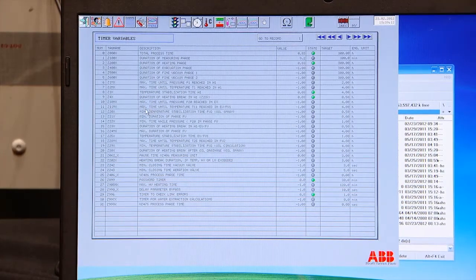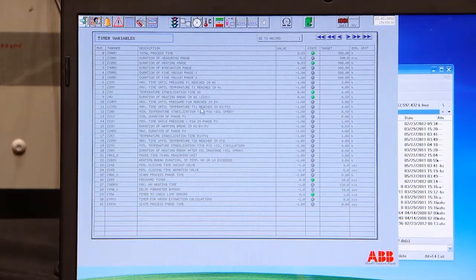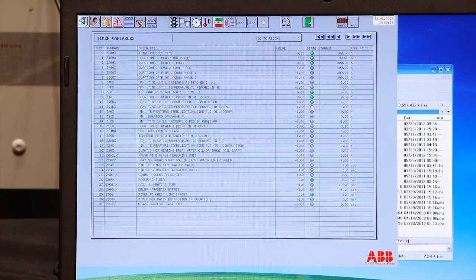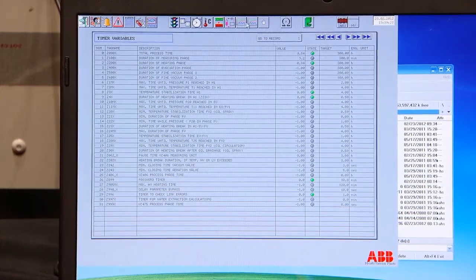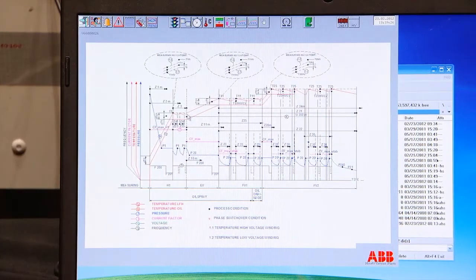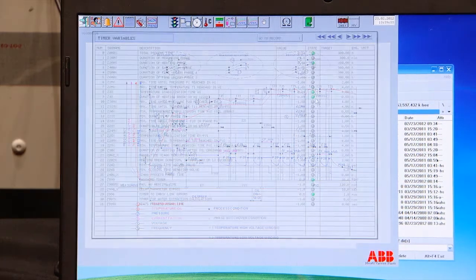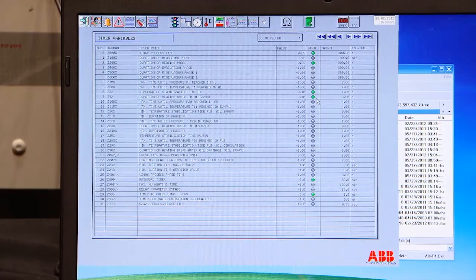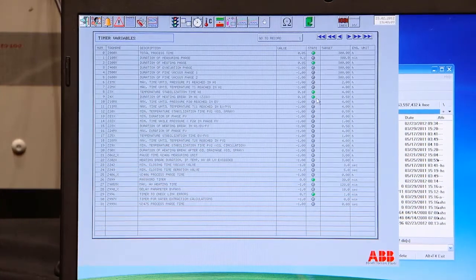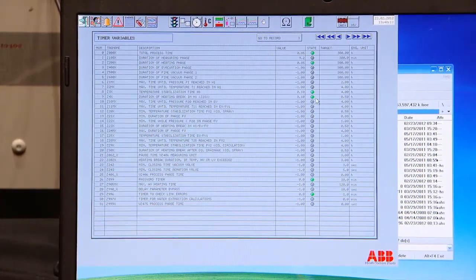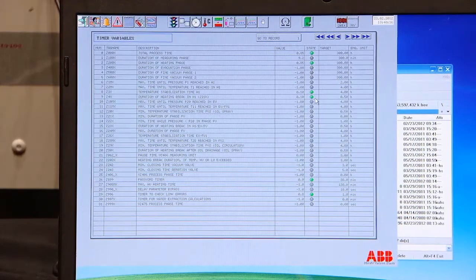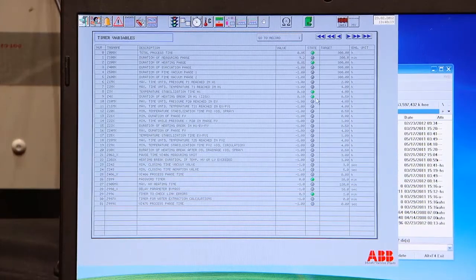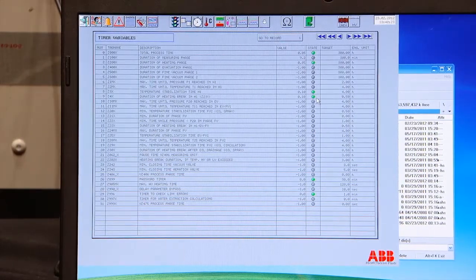Maximum time, 2 hours, isn't it? 4 hours it's set to. Maximum time until temperature T11 is reached in evacuation fine vacuum. So if it takes more than 4 hours to go from the set point we have now, 65 degrees, up to the fine vacuum set point, you will have an alarm. The system is unfortunately working on a base of 10. So even time is working on a base of 10, which means 0.5 hours is half an hour, it's not 50 minutes. 0.7 hours is 42 minutes. It can be confusing when you're setting the timers, but it's important to remember that that's how it's working.